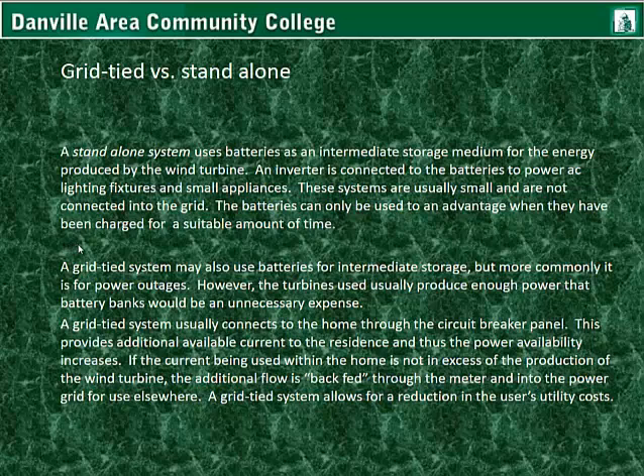A grid-tied system may also use batteries for intermediate storage, but more commonly batteries are used for power outages. However, the turbines used usually produce enough power that battery banks would be an unnecessary expense for larger grid-tied systems. A grid-tied system usually connects to the home through the circuit breaker panel, or load center. This provides additional available current to the residents. If the current being used within the home is not in excess of the production of the wind turbine, the additional flow is back-fed through the meter and into the power grid for use elsewhere, reducing utility costs.